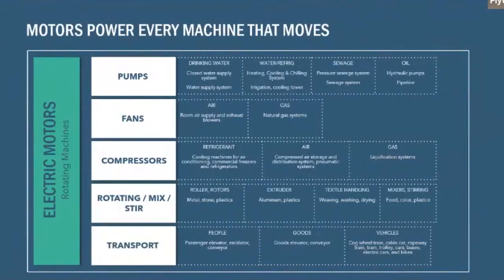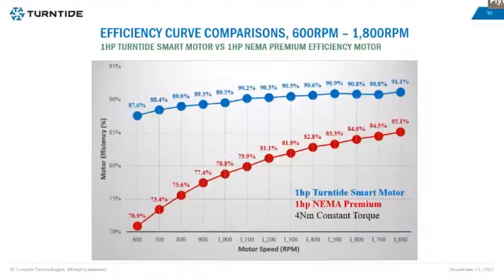We believe we can do that with our HR-SRM technology, because not all motors today are very high efficiency. For example, a one horsepower NEMA standard motor for the USA has an efficiency of 85.1%, but that's only at rated conditions. When you operate that on a fan, which has a cubic relationship between speed and power, running at half the speed means the power is only one-eighth.